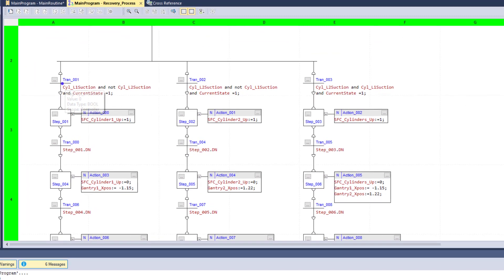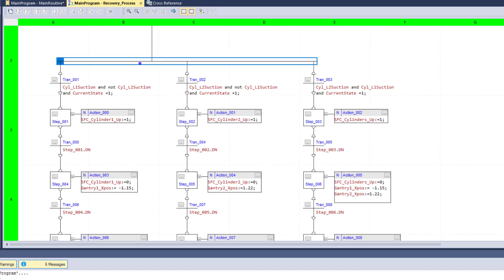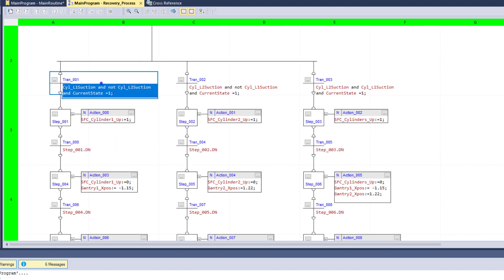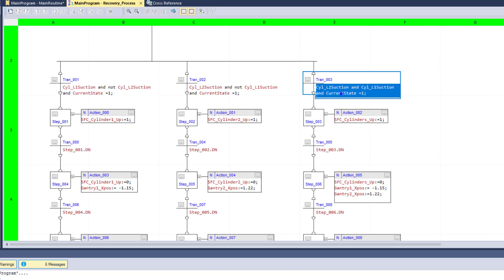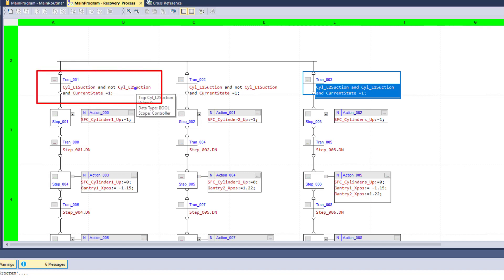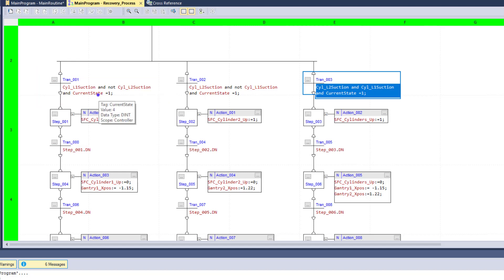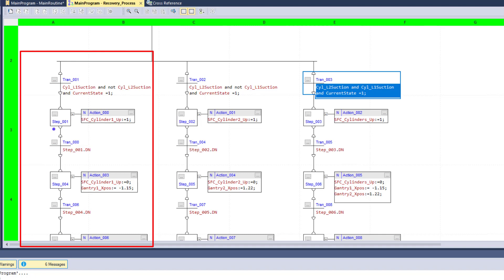When we come in here, we understand we have three different branches. We have this first parallel branch that branches over and makes a decision. The decision makers are right here — transition one, transition two, and transition three. What we're doing is saying if the suction is on the first cylinder but not on the second cylinder, and the system is in state one — meaning the start button has been pressed, the door is shut, everything is active — then it will allow it to go down this string.